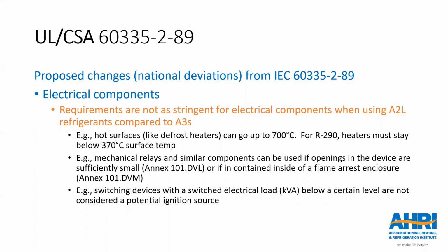Mechanical relays and similar components normally considered a potential ignition source are allowed with A2Ls if the openings in the device are sufficiently small or if they are contained in a flame arrest enclosure. And this is because a flame cannot physically propagate outside of the device in those instances. Additionally, switching devices with a switched electrical load below a certain level are also not considered potential ignition sources for A2L refrigerants.